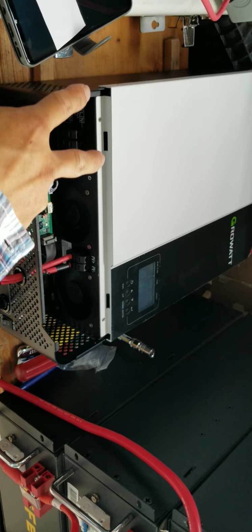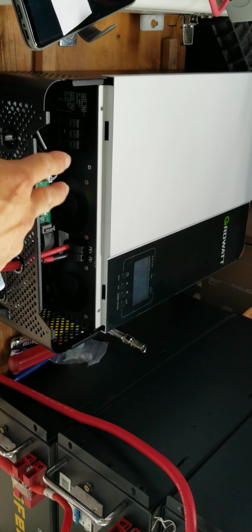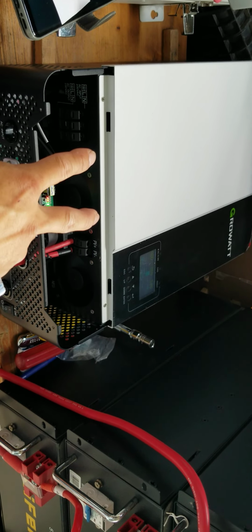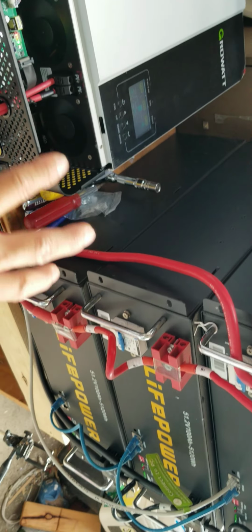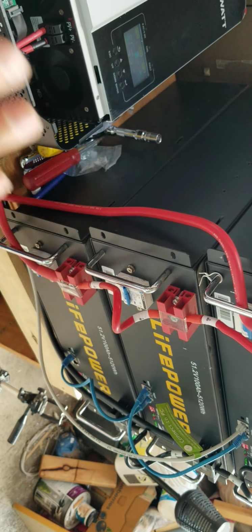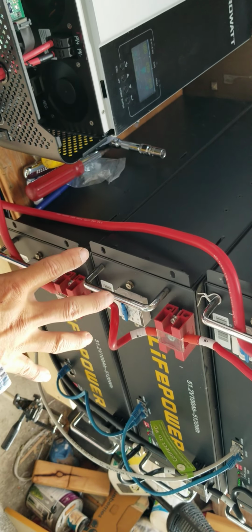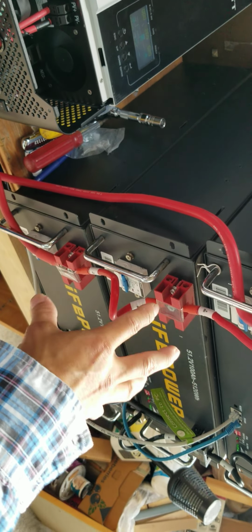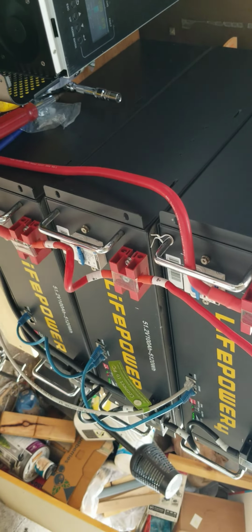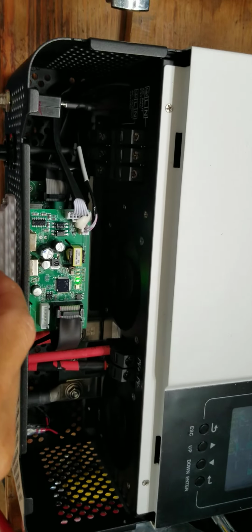The communication of the BMS of the inverter should say, okay, this battery is low, you should give it maximum up to 6000 watts, because the battery is so low, and I have 3 of them, not 1 but 3. So you guys get my point, right?